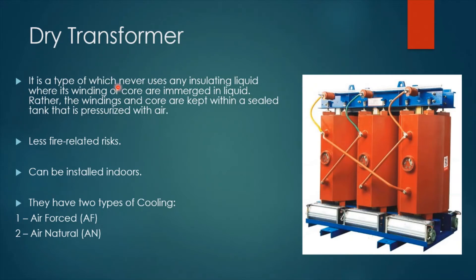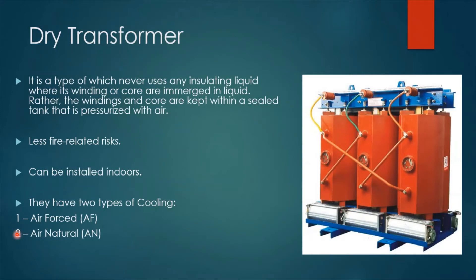A dry type transformer never uses any insulating liquid in which its winding or core are immersed. Rather, the windings and core are kept within a sealed tank that is pressurized with air. It has less fire-related risks and is safe to be installed inside buildings. Dry transformers have two types of cooling: air forced (AF), which is equipped with fans to cool down the transformer, and air natural (AN), which does not utilize any fans but relies on natural air.